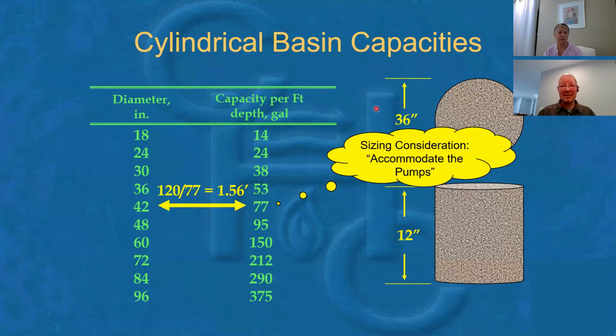If I know that, now I'm looking at a 42-inch diameter basin, which holds 77 gallons per foot. I need about 1.6 feet. And don't ask me to do that. That's 12 plus 6. That's 18 inches of usable water within a 42-inch diameter basin.